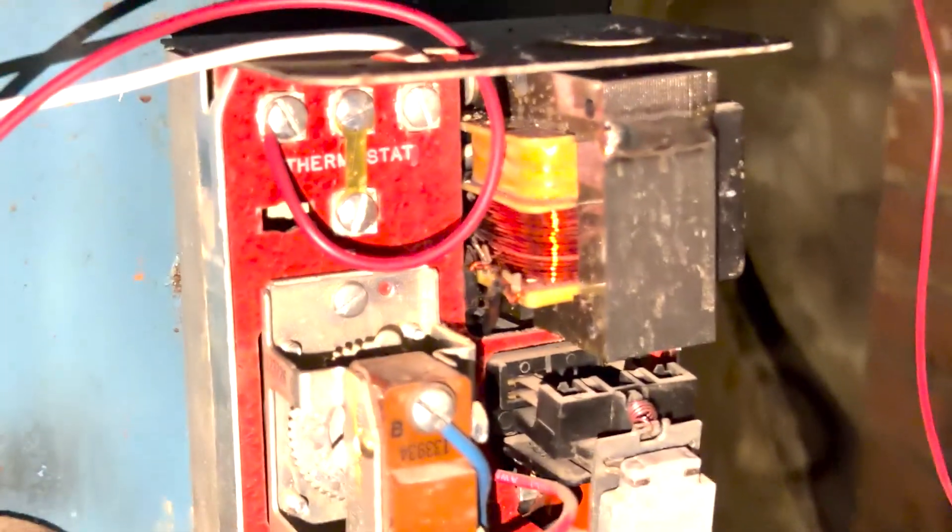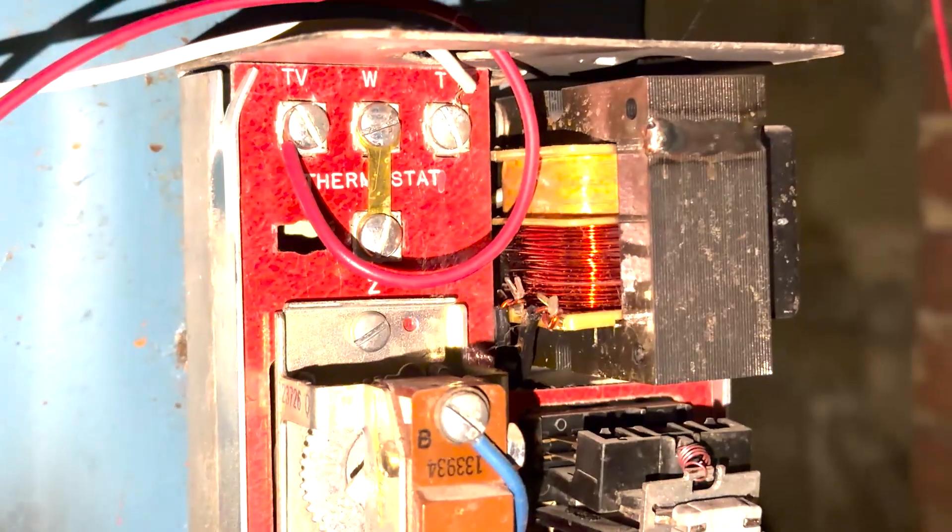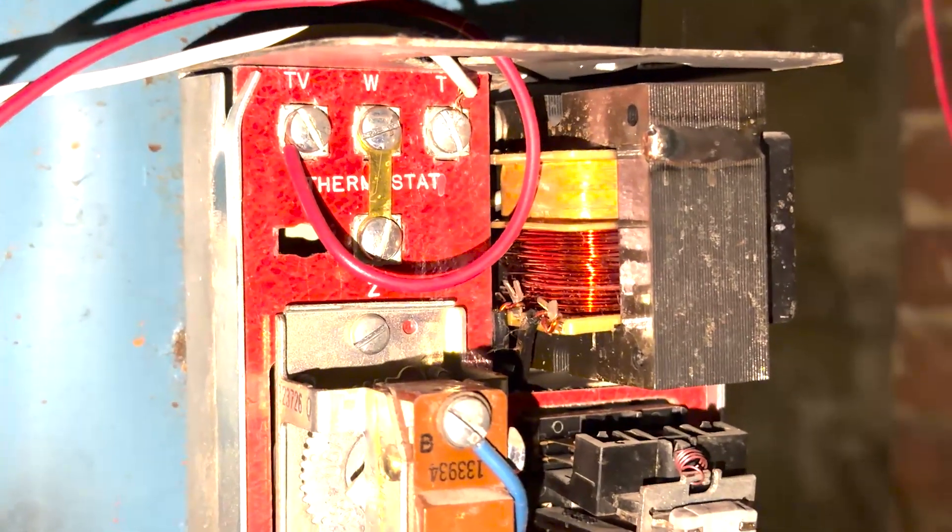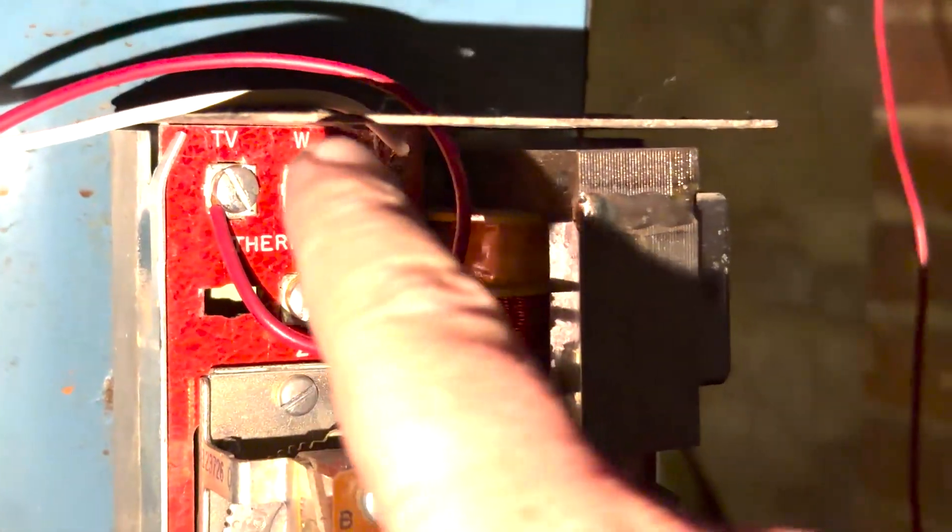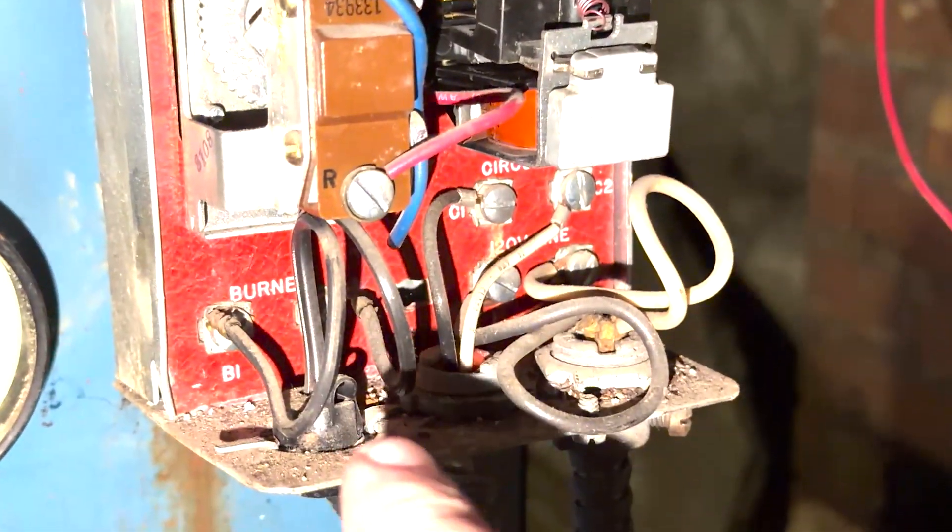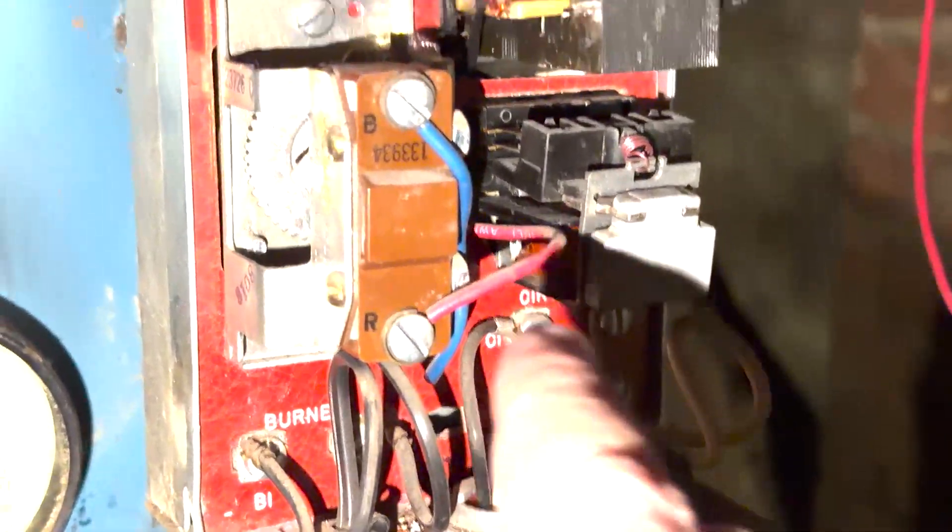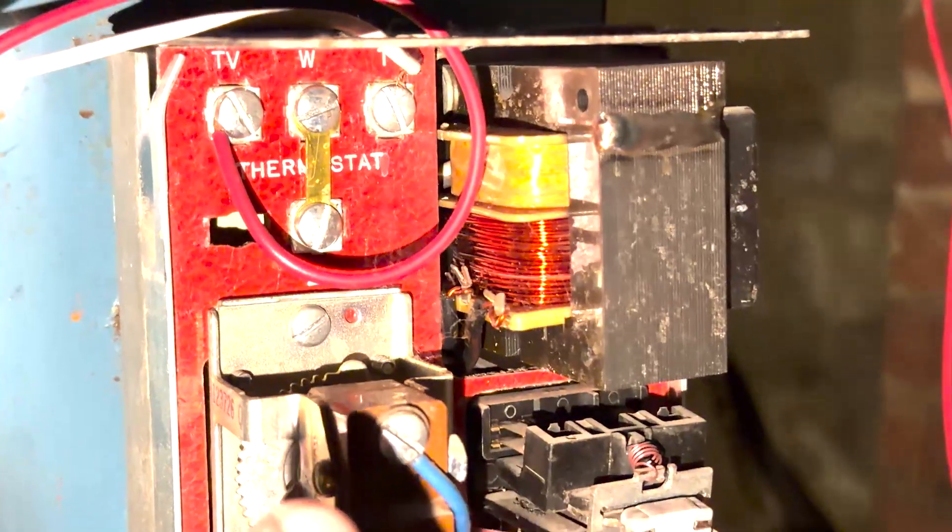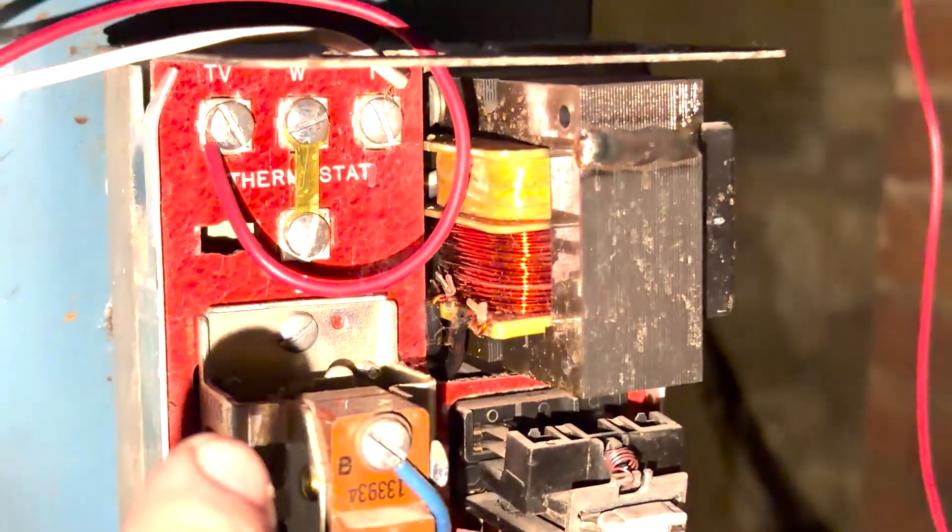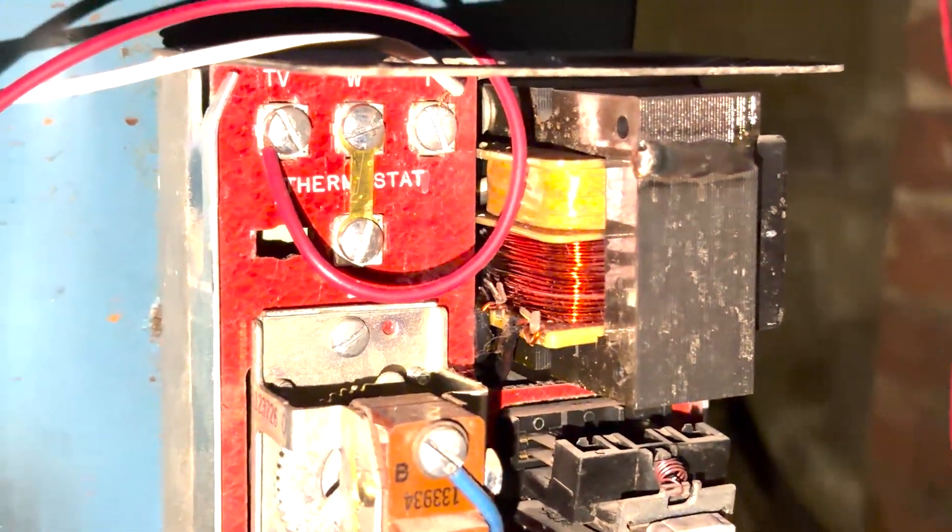So this is the Aquastat box and you'll notice when you look inside here that it doesn't look like your typical newer age models. These connectors are labeled differently and there's a whole bunch of other stuff going on here. The main important thing is that there is no C-wire that's going to come off of here which you need for the Ecobee.